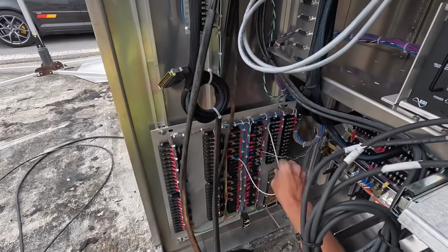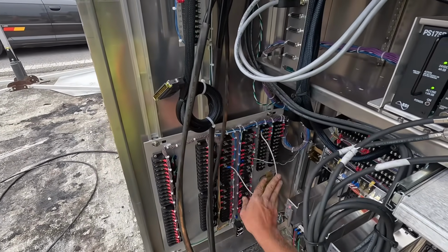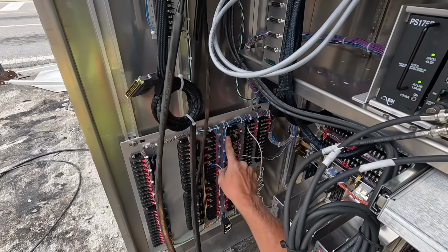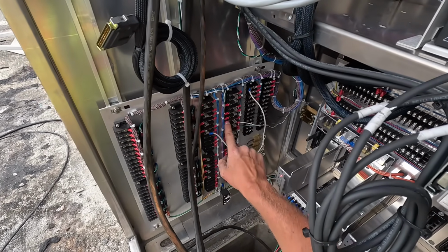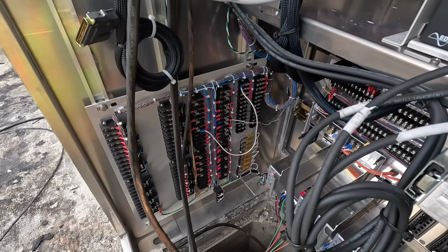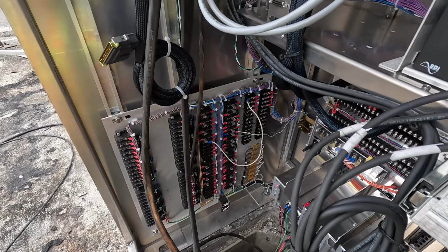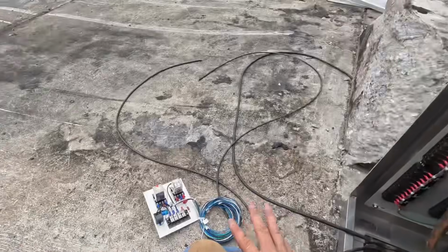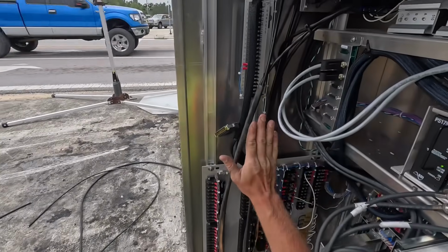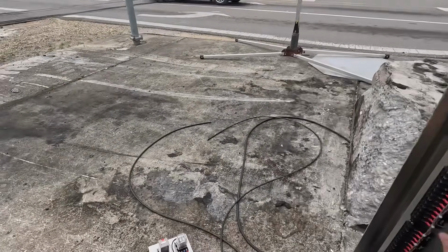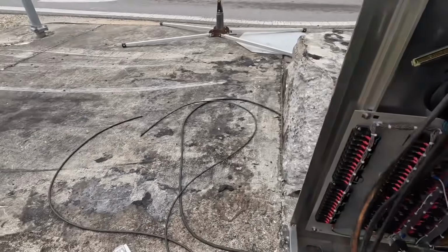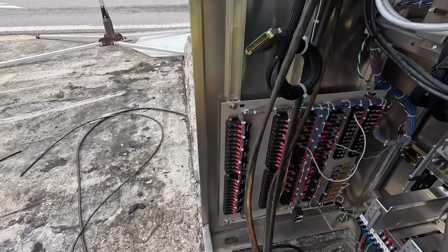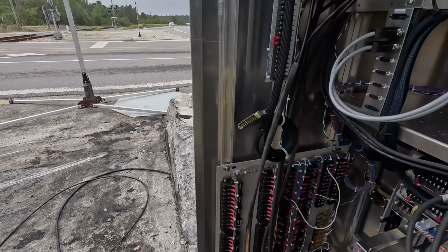Right here on the side panel, not where this is jumped out, but right over here, these three lugs here have 120 volts. This would be our neutrals, and then our grounds below it. So what we can do now is wire this up, preferably on this side of the cabinet. And we'll find a good little location for it. Run our cables down, wire it in. I'm gonna leave a lot of extra slack in case we relocate it when we relocate the cabinet.